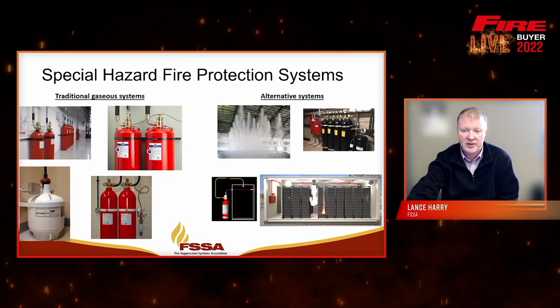In the bottom right, you have an aerosol system, a slightly different type of system that does not use a centrally stored pressurized container. These are small canisters installed throughout the protected space, each discharged at the same time to produce enough density of aerosol to put a fire out. Here we see it depicted in an energy storage container, a fairly common application for aerosol systems, as well as several other types of systems.